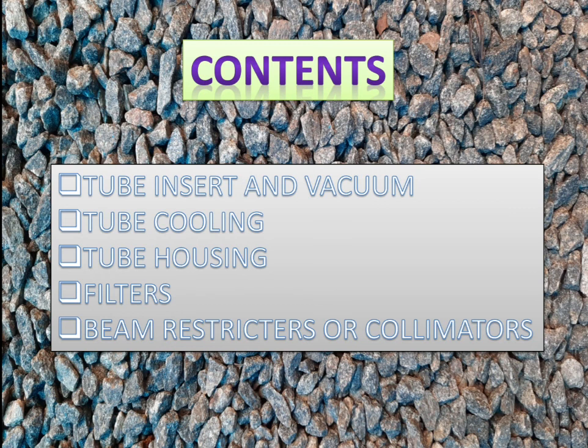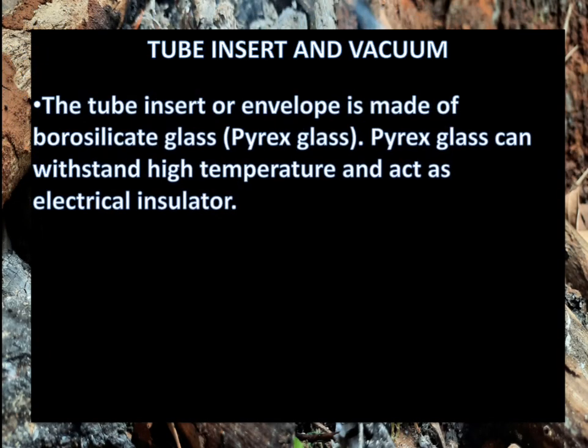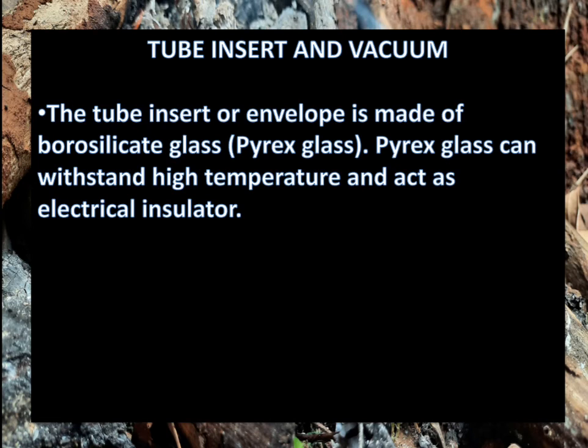First, we shall look into tube insert and vacuum. As we learned in the x-ray tube video, the x-ray tube is inserted inside a lead case filled with coolant oil, and the x-ray tube itself is made up of a glass envelope. This glass envelope is the tube insert, made up of a special type of glass known as borosilicate glass, commonly called pyrex glass.